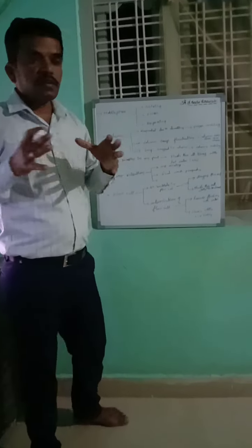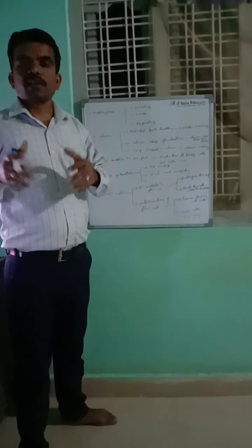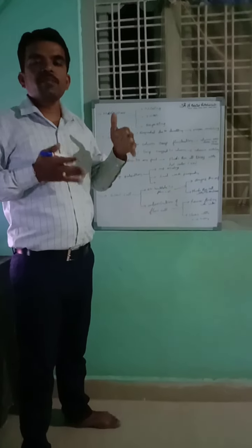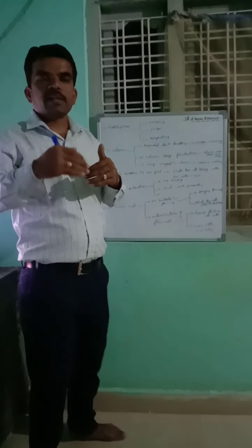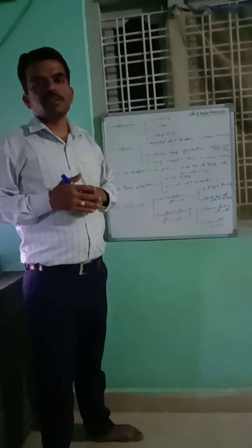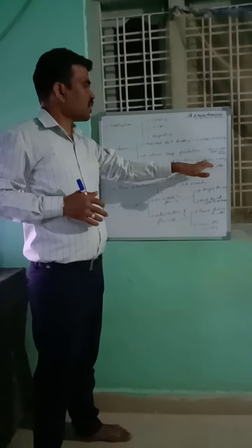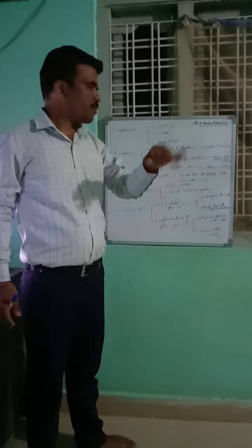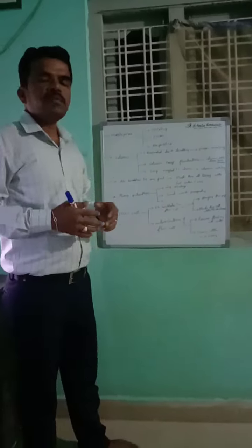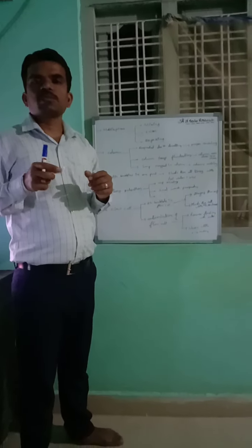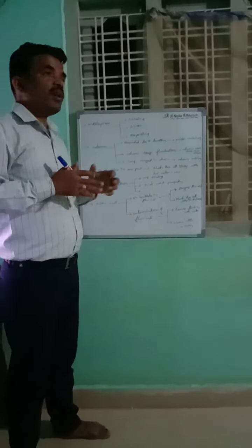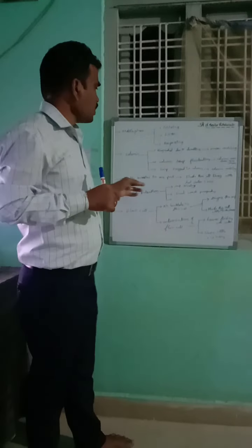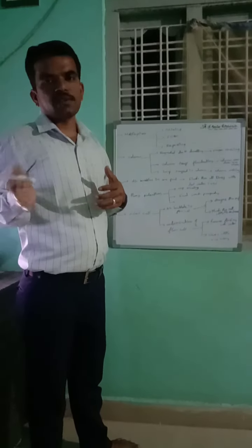And one more reason is that impurities may be trapped in our column. Impurities from previous analyses may be trapped in the column, and due to that you will get some noise. For that purpose, we have to wash the column properly. When the column is degraded due to dewetting, we have to wash the column properly. If column temperature fluctuations are there, we have to ensure that the door is closed properly, and we have to maintain the room temperature in a consistent mode. And if impurities are trapped in the column, you have to wash the column properly.